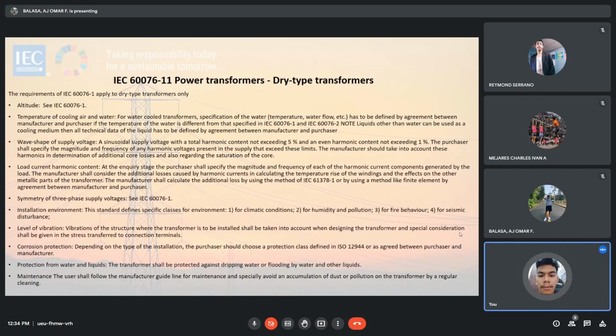Dito naman sa symmetry of three-phase supply voltage, nandun pa din siya sa 60076 Part 1. So, general standard pa din siya. Installation environment, this standard defines specific classes for environment. First is yung climate condition, humidity and pollution, for fire behavior and seismic disturbances. Level of vibration. Vibrations of the structure where the transformer is to be installed shall be taken into account when designing the transformer. Special consideration shall be given to the stress transferred to connection terminals.